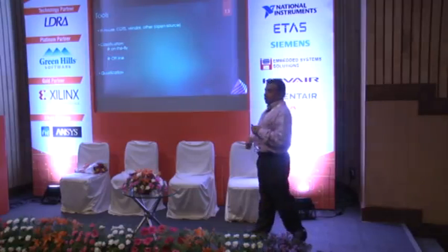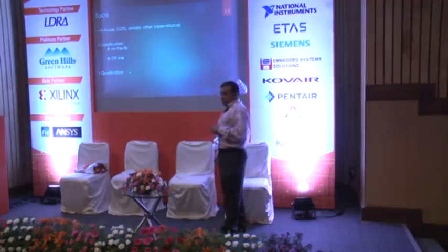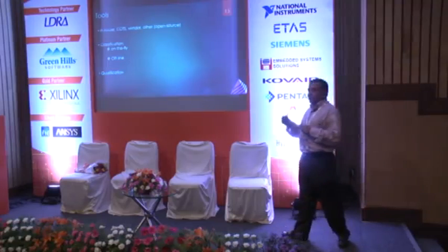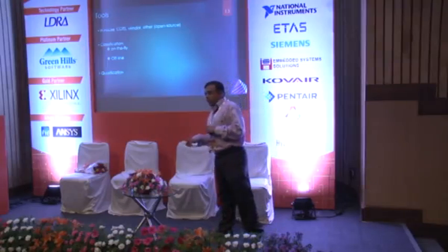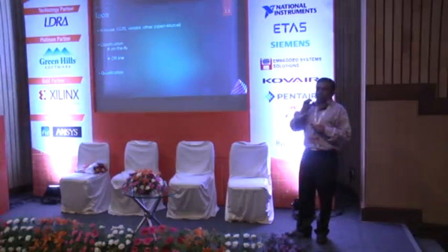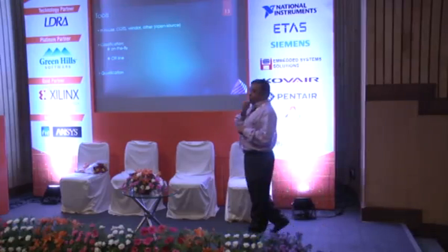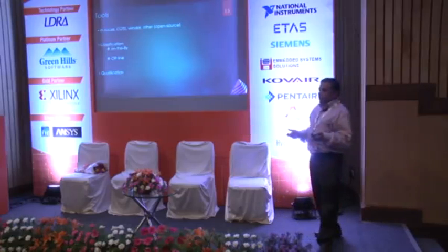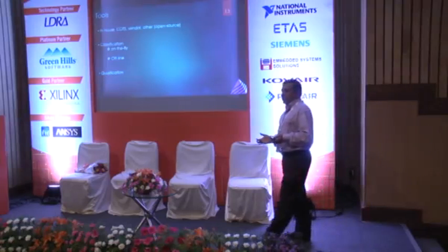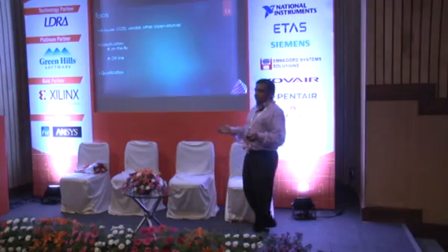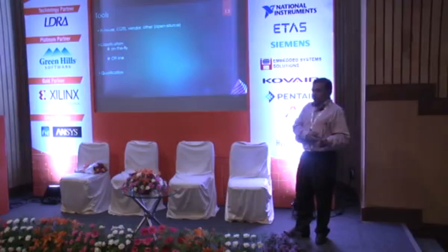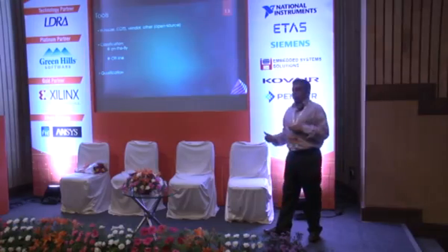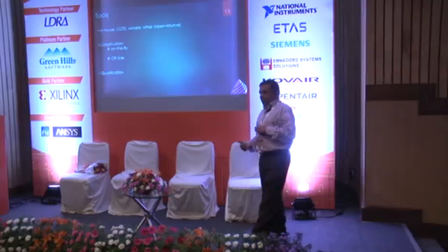So either of them, if you are going to use in your system, they have to go through the qualification process. Okay, which means if I have to use them, they have to be qualified, and the meaning of qualification here is, are they fit to be used in my project and whether they can take care of my safety requirements. Eventually the whole thing is pointing to the safety expectations. So the qualification could come from what is the process followed for developing the tool, whether that process has been following 61508 standards, or it has been proven in use. Maybe my company has been using that for the last 10 years, okay, and it has not given any issues so far, and hence I am confident about that. So there are various categories which 61508 defines, wherein you can say the tool is qualified to be used in my safety system for this particular project.